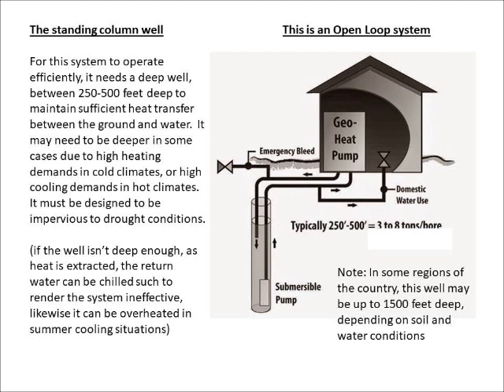For this system to operate efficiently, it needs a deep well between 250 to 500 feet deep to maintain sufficient heat transfer between the ground and water. It may need to be deeper in some cases due to high heating demands in cold climates or high cooling demands in hot climates. It must be designed to be impervious to drought conditions. If the well isn't deep enough, as heat is extracted, the return water can be chilled such as to render the system ineffective. Likewise, it can be overheated in summer cooling situations. And in some other regions of the country, this well may be up to 1,500 feet deep, depending on soil and water conditions.